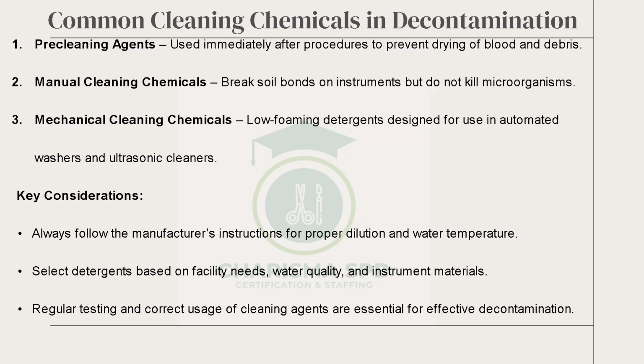Good job. So you see that it goes back to the manufacturer's instructions when you get there. Pre-cleaning agents used immediately after procedure. That's mostly they're going to do it before the instruments get to the decon. Manual cleaning, you're going to be using it, which breaks the soil bonds on instruments, but does not kill microorganisms. Put that at the back of your head. And that is why I refuted the 100% answer that Obi gave me earlier. It's going to break the bonds on instruments, but it does not kill the microorganisms. All right? Then it goes into the mechanical cleaning, where the low foaming detergents designed for use in these machines will clean it. Okay? So your consideration is that you follow the manufacturer's instructions, we call them the IFUs, information for use.